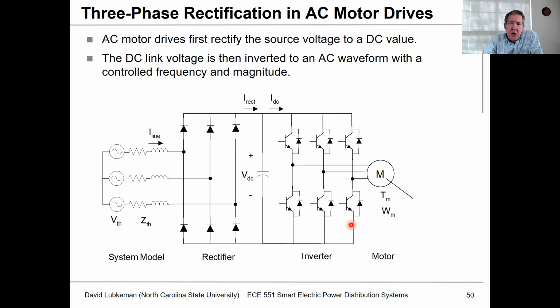We talked a little bit already about rectification for motor drives. And so when you have a motor drive, you convert the AC into DC, then you convert the DC back to AC. And by changing the frequency and the magnitude of the voltage applied to the motor, you can control the torque and the speed. And these are all controlled switches on the motor side, on the inverter side of this.